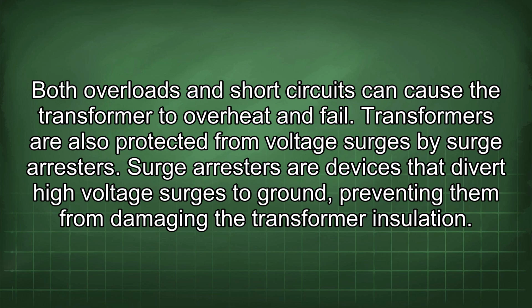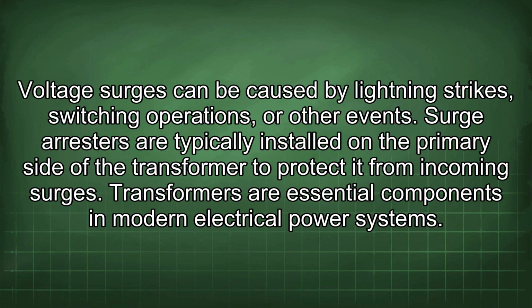Transformers are also protected from voltage surges by surge arresters. Surge arresters are devices that divert high voltage surges to ground, preventing them from damaging the transformer insulation. Voltage surges can be caused by lightning strikes, switching operations, or other events. Surge arresters are typically installed on the primary side of the transformer to protect it from incoming surges.